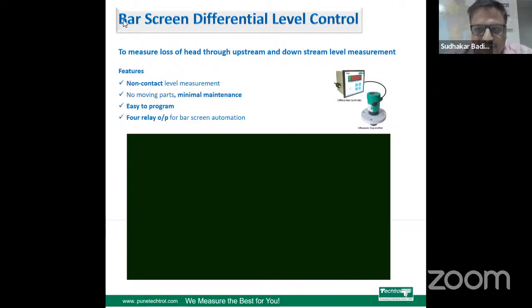So this difference is set in this controller. At the particular set point, once the difference has increased, it gives the command to the actual bar screen, which has a mechanical arm to remove the garbage that is stuck in the net. So it is continuously removing the garbage. Once the garbage has been removed, the water automatically starts flowing freely through the net, and then both the upstream and downstream levels become similar. So this is the purpose of automation in the bar screen control. We'll just show you the video also.